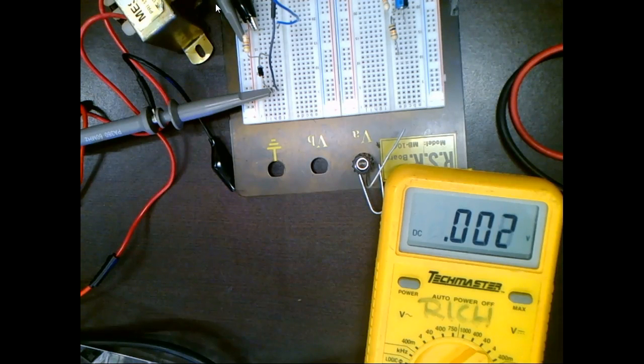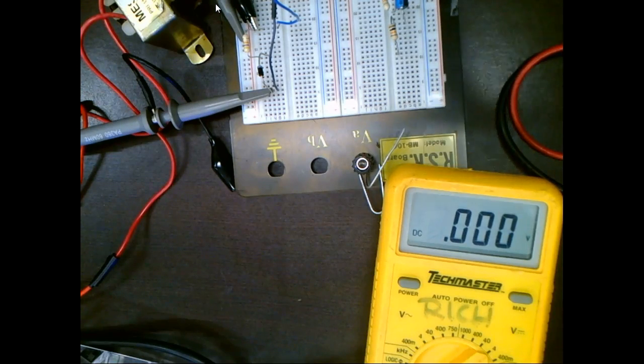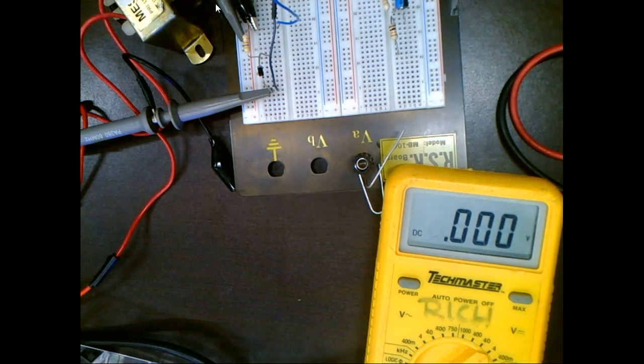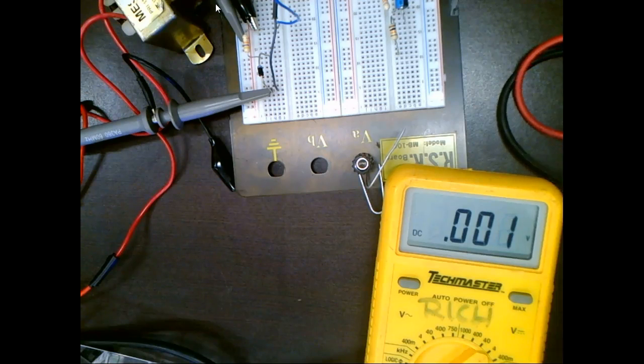So with 240, the power does not use ground, even though you bring ground out and hook it up to the chassis of the metal, to keep your water heater from becoming electrically hot if something happens. But 240 is not referenced to ground, while 120 is, you understand that? So all your 240 devices, the loads themselves, are not referenced to ground.